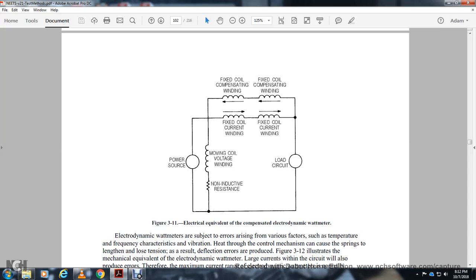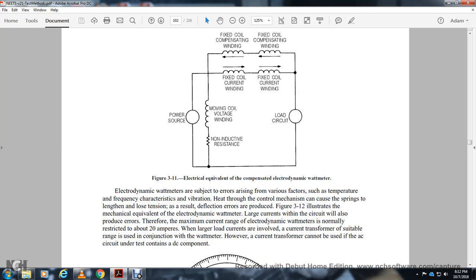A typical electrodynamic watt meter has a power source, moving coil voltage winding, non-inductive resistance, load circuit, fixed coil current winding, and compensating windings. Electrodynamic watt meters are subject to error from various factors including temperature, frequency, vibration, and heat affecting the control springs. Large currents in the circuit also produce error. The maximum current range of electrodynamic watt meters is normally restricted to about 20 amperes. For larger load currents, a current transformer suitable for use with the watt meter is employed.